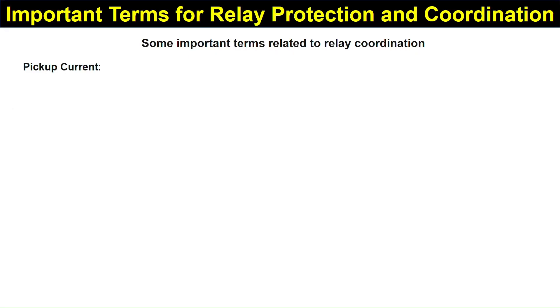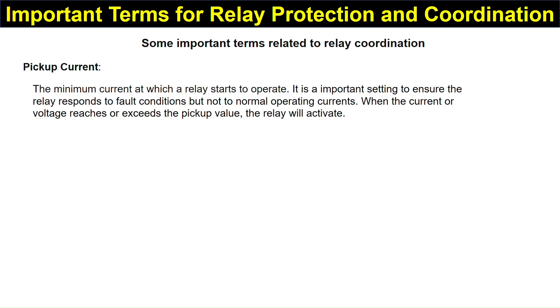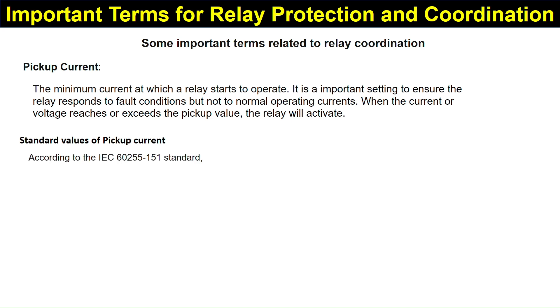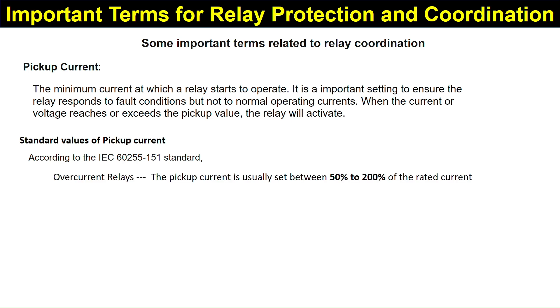The first term is pickup current. This is the minimum current at which a relay starts to operate. It is an important setting to ensure that a relay responds to fault conditions but not to normal operating currents. When the current or voltage reaches or exceeds the pickup value, the relay will activate.